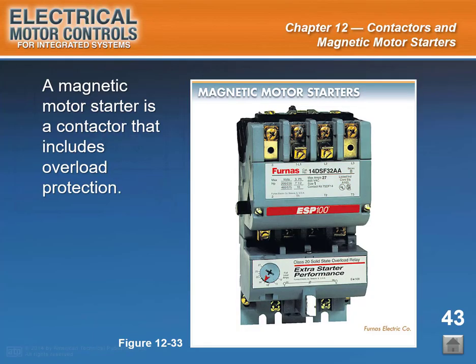Start of slide 43. Slide caption: A magnetic motor starter is a contactor that includes overload protection. See Figure 12-33. A magnetic motor starter is any electrically operated switching contactor that also provides some sort of motor overload protection. Magnetic motor starters include overload relays that detect excessive current passing through a motor and are used to switch all types and sizes of motors. Magnetic motor starters are available in sizes that can switch loads of a few amperes to several hundred amperes. End of slide 43.